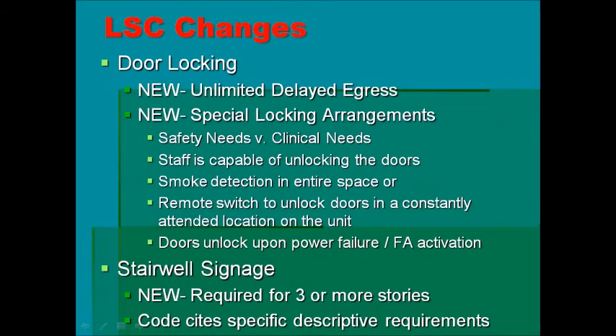One of the great changes with the Life Safety Code when it comes to delayed egress locks, under the 2012 edition of the code, previously under the 2000 edition, you were only allowed to have 1 delayed egress device in any single means of egress. Today, you can have more than 1 delayed egress device in any single means of egress. So if you have a secure unit in the middle of your building where you need to put a delayed egress device, and you also need to put one on the outside exit from the building, in the past that would be considered non-compliant. Under the new code, it is compliant.